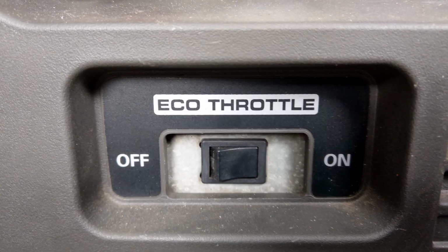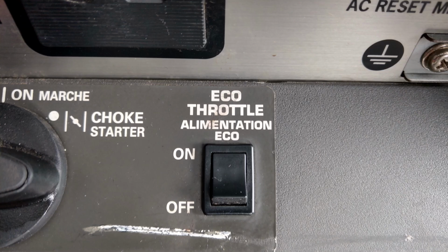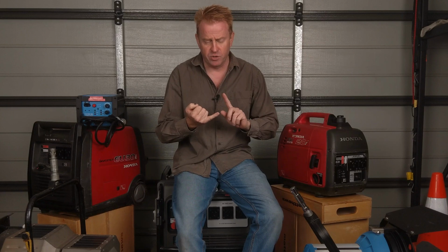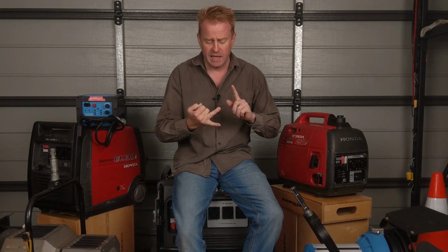The next thing to talk about is eco throttle. So basically, eco throttle determines whether the engine is running at a constant full speed or if the engine is allowed to rev down when there's not as much draw on the generator and then rev back up if more power draw is required. So the Eco Throttle has three advantages. It reduces your fuel consumption. It reduces the noise level off the generator because it's not running as hard, and it can increase the longevity of your motors because they're not running as hard. However, it does have some disadvantages depending on the situation you're working in.